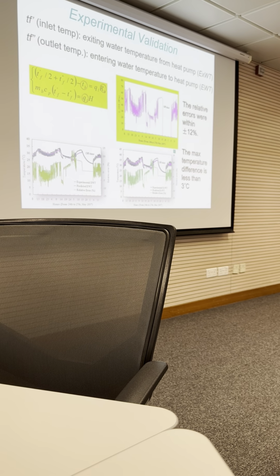Usually we check the exiting water temperature from the heat pump. Exiting water temperature means the entering temperature to the borehole. Another one is the entering water temperature to the heat pump, which means the exiting water from the boreholes. Then we compare our simulation result from the analytical solution with the experimental result. Then the error is only 3. The maximum temperature difference is less than 3 degrees Celsius. Then this is interesting.